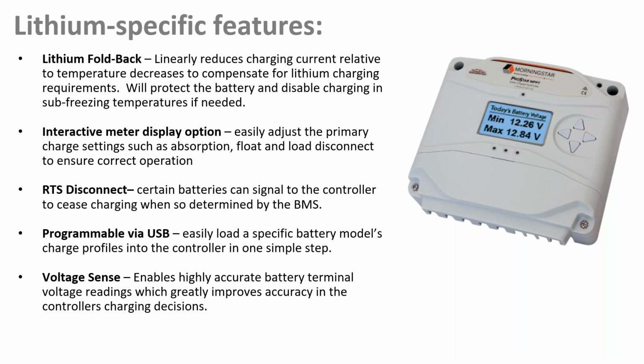But in industrial applications, occasionally if you dip below freezing, the controller can reduce linearly the amount of charge current so the battery does not see excessively high charge rates in cold temperatures. When the battery warms back up and cycles throughout the day, it will actually increase back, which you can see shown in some later screens.